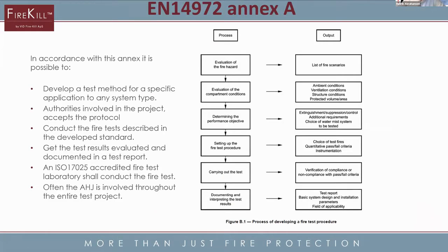What happens if you don't have a standard covering your application? Then you can use Annex A, which is basically how to develop a fire test procedure. This can be done as a cooperation between AHJs, test facilities, ISO 17025 accredited laboratories, owners, manufacturers, etc. If you evaluate the fire hazard, you will have a list of fire scenarios; you evaluate the compartment conditions like ventilation, structural conditions, volumes, and areas; you determine the performance objective — do you want extinguishment, suppression, or control — then you set up the fire test procedures.